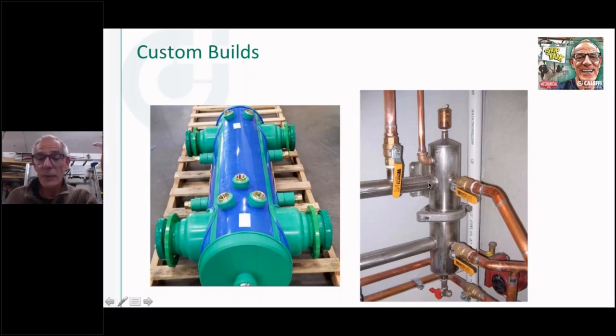So he came in once, and that'll work. They don't have to be directly across from one another. And also some of the manufacturers will actually offset them a little bit when they come in here. That's fine too. But this works great. So there's his air elimination. I don't know that he put anything inside here when he built it. I never did see it as he was constructing it, but there's an example of you just use the math, use the formula that I gave him, and came up with the right size tube and the piping to build it out of stainless.